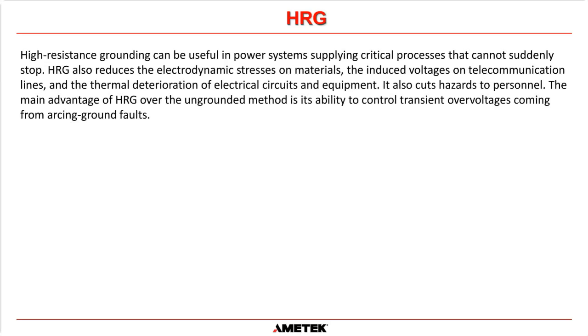The main advantage of a high resistance ground system over an ungrounded method, where the ungrounded method means there are no connections to ground in the system, is the ability to control transient overvoltages coming from an arcing ground fault. Okay, and it also allows you, because in most high resistance ground networks you will have a lamp or some kind of detecting circuit that will tell you that there has been an unintentional ground created on that system. So it allows you to find things and go to them and maintain them.